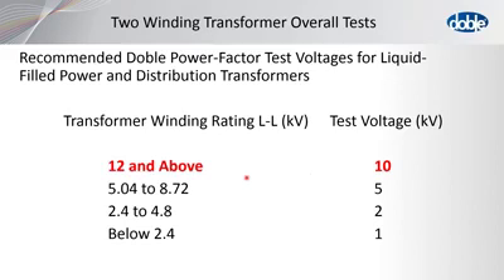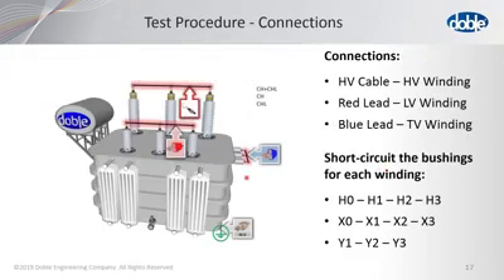Remember, test voltage, we want to make sure that we use the proper test voltages. These are published in our books and in DTA, but the main thing to remember is if your winding is rated greater than 12 kV, you can test at 10 kV. Any other lower voltages, you want to look it up. So, test procedure. Now, one thing we want to make sure that you do is to short the windings, because not shorting the windings can cause some unusual test results. So we short the high side, we short the low side, and short the tertiary.